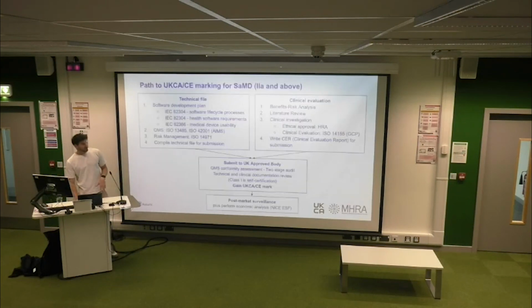and then write this all up in your clinical evaluation report and clinical evaluation file, and then you would submit these to the approved body who would do their conformity assessments, assess your technical and clinical documentation, and then grant your UKCA. Well, they would certify you, and then you could register and get your UKCA or CE mark in Europe. And then it's not over then.